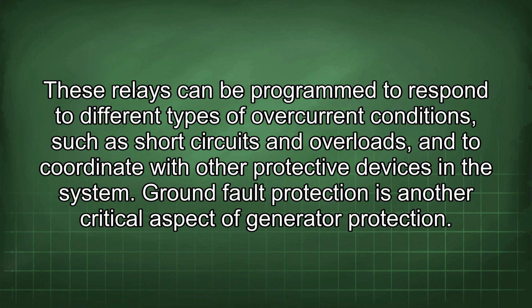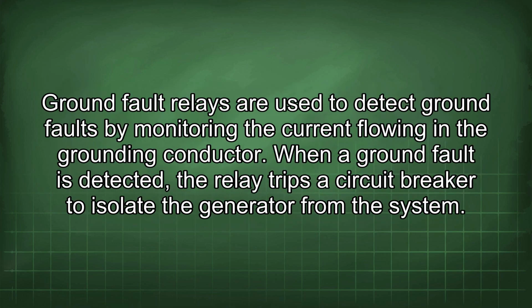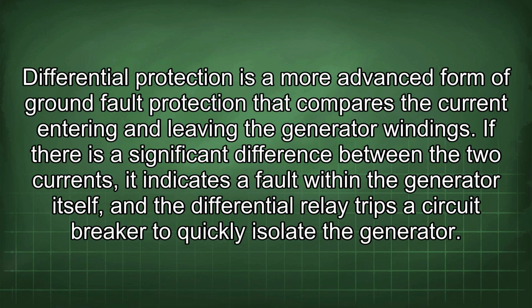Ground fault protection is another critical aspect of generator protection. Ground fault relays are used to detect ground faults by monitoring the current flowing in the grounding conductor. When a ground fault is detected, the relay trips a circuit breaker to isolate the generator from the system. Differential protection is a more advanced form of ground fault protection that compares the current entering and leaving the generator windings. If there is a significant difference between the two currents, it indicates a fault within the generator itself, and the differential relay trips a circuit breaker to quickly isolate the generator.